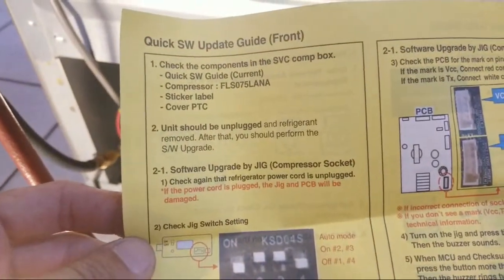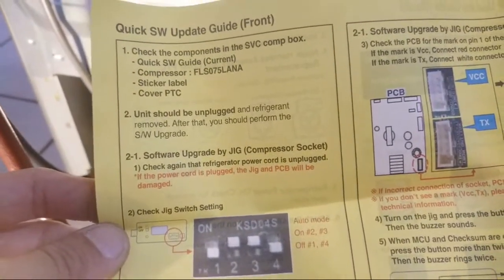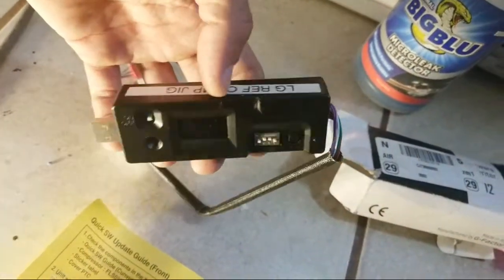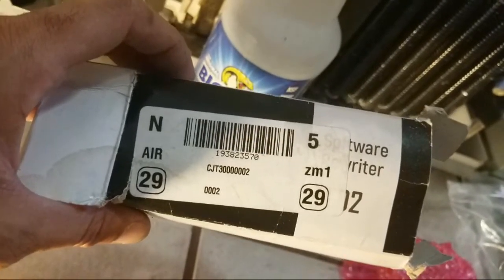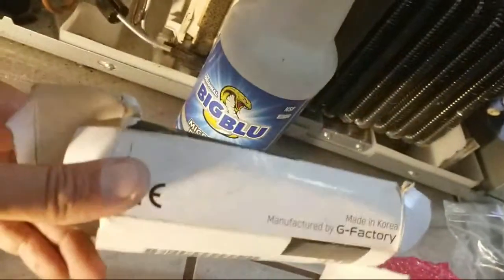Step two: the unit should be unplugged, then you perform the software upgrade - check upgrade by jig compressor socket. No one told me this until I learned it on my own, but this is the jig you need to program the board. If you don't have the jig, the part number is Charlie Juliet Tango 3-0-0-0-0-0-0-2.